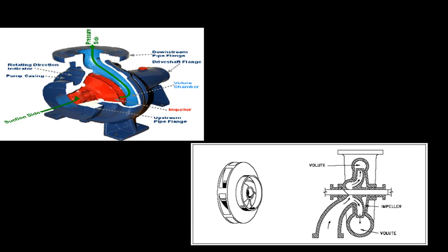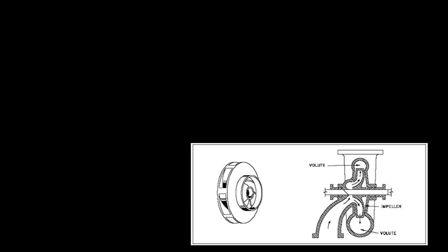Centrifugal pumps are often associated with the radial flow type; however, the term can describe all impeller-type rotodynamic pumps including radial, axial, and mixed flow variations. Radial, mixed, and axial flow pumps belong to the class of rotodynamic machines. In a radial flow pump, fluid entering along the axial plane is accelerated by the impeller and exits at right angles to the shaft. Radial flow pumps operate at higher pressures and lower flow rates than axial and mixed flow pumps.